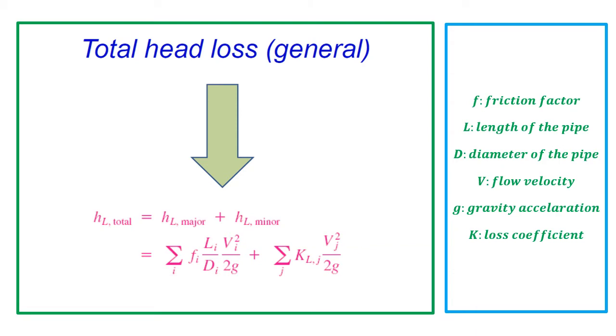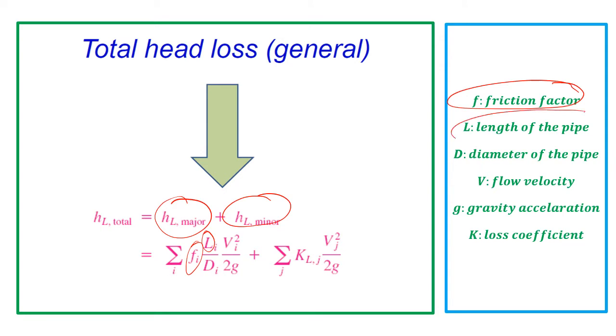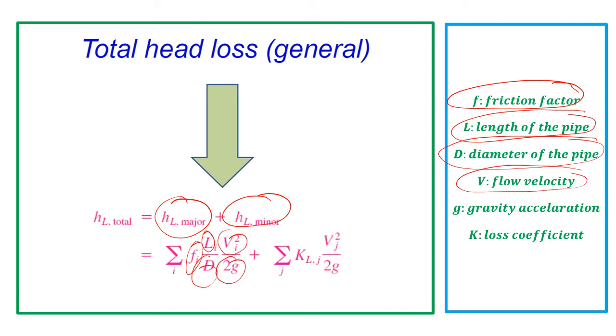So the total head losses is the sum of major losses and minor losses. Major losses can be found by the equation where F is the friction factor, L is the length of the pipe, D is the diameter of the pipe, V is the flow velocity in the pipe, and 2G is twice the gravitational acceleration. For minor losses, we have KL which is the loss coefficient, V is the flow velocity, and 2G is twice the gravitational acceleration.